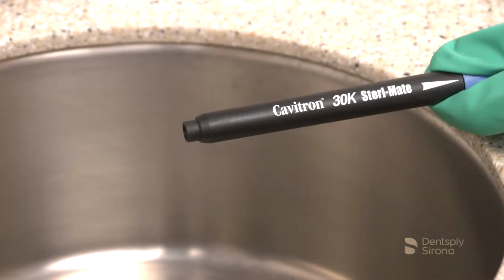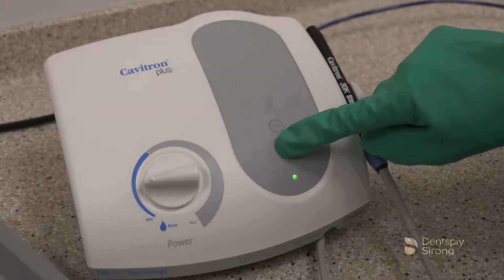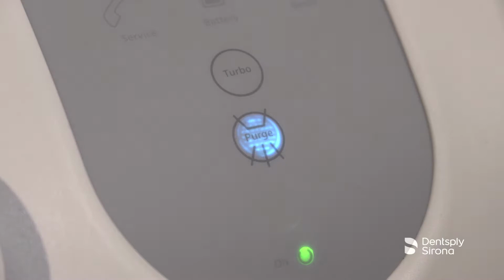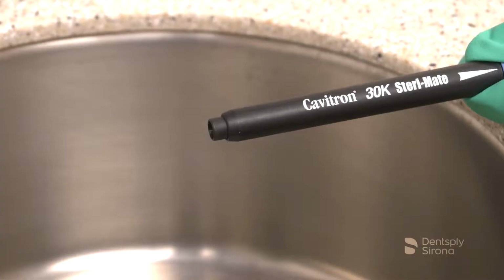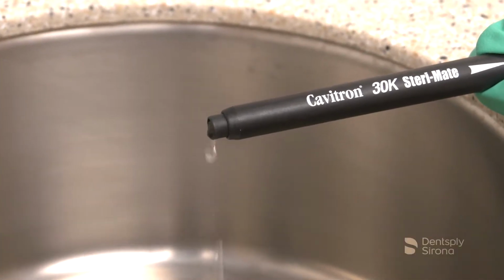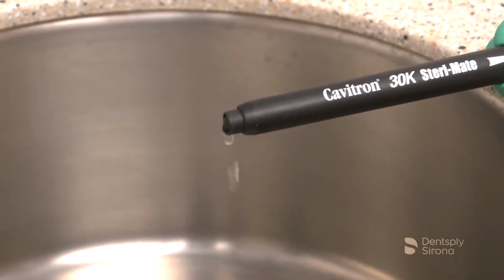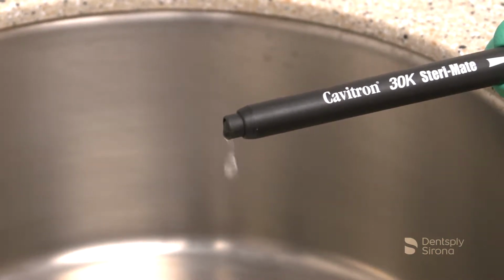Hold the handpiece over a sink or drain and activate the purge control button. The purge function will run for 2 minutes. This function will flush out any stagnant water that remained in the lines overnight and releases any air bubbles that may be trapped in the handpiece.